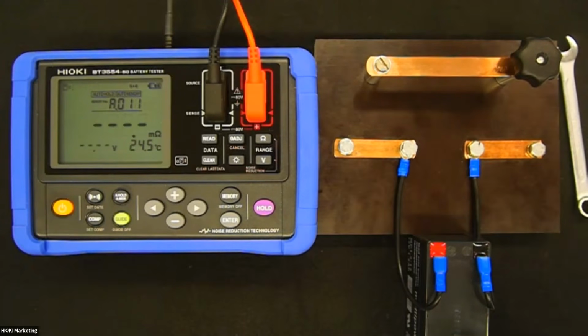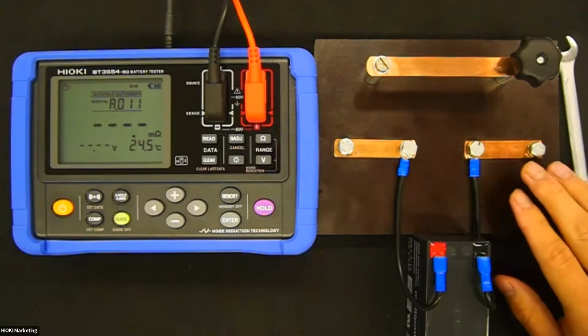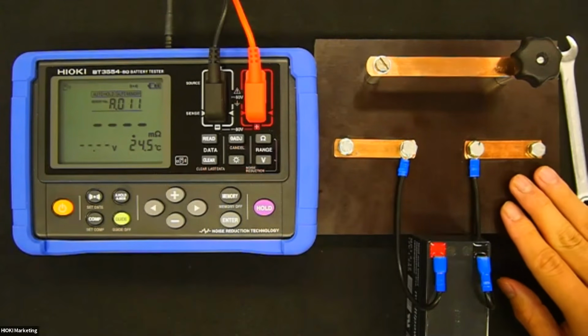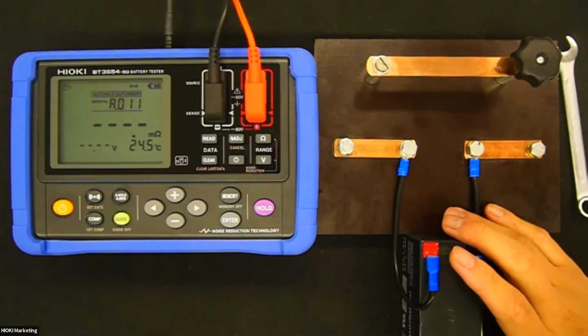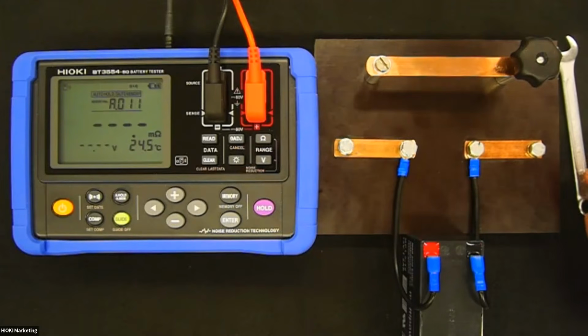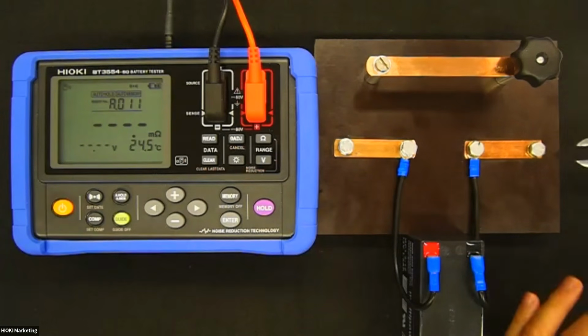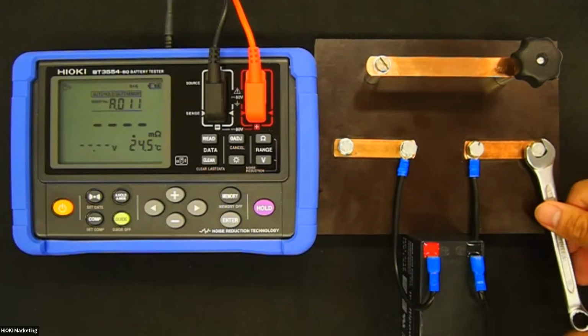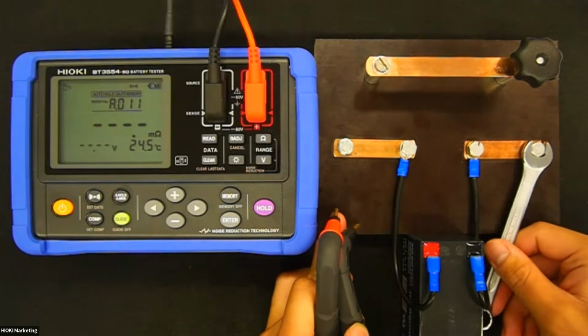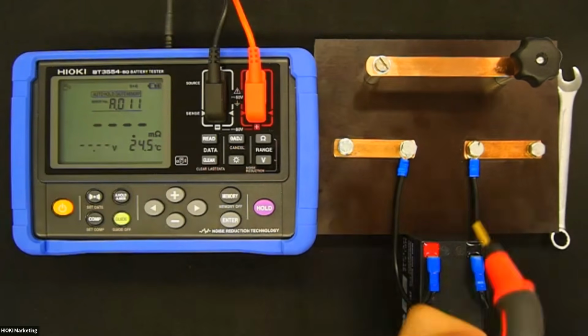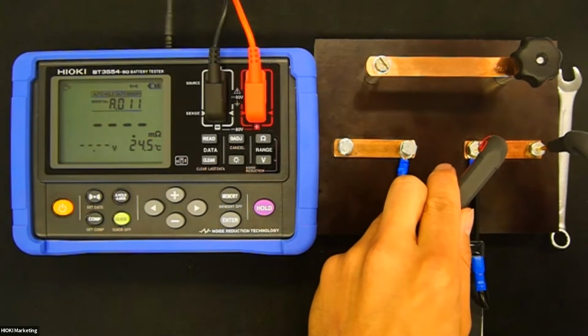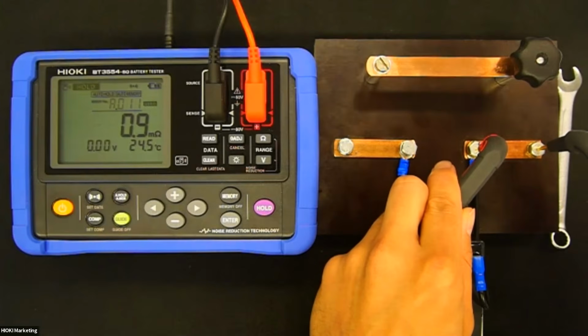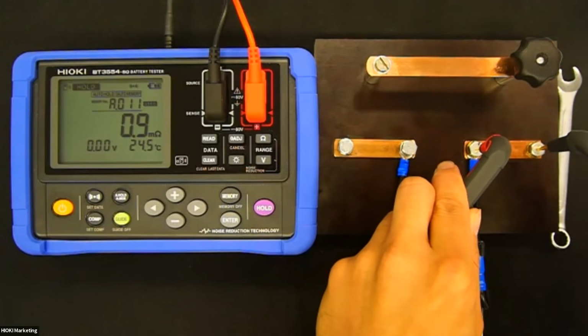So connection resistance is an important test item for battery maintenance. You should check the contact resistance using the battery tester, because it's very good for checking low resistance values, as you can see. Now I've fixed the bolt again and checked the contact resistance—now it shows less than 1 milliohm.